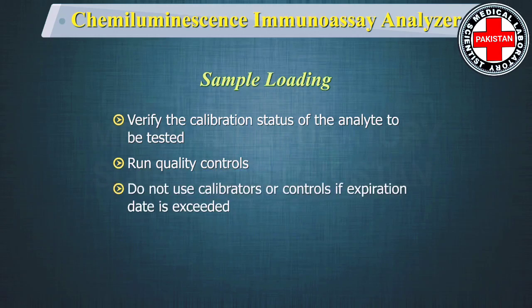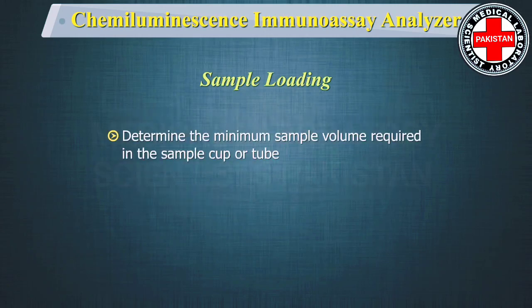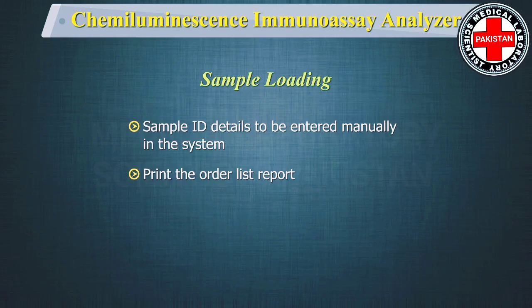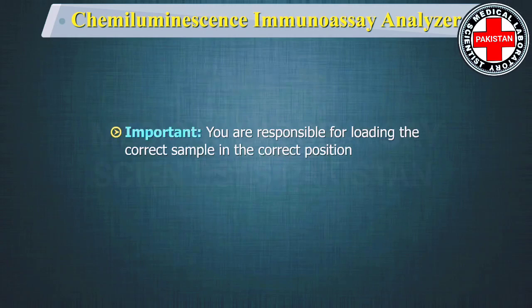Before loading test samples, verify the calibration status of the analyte to be tested. Also run quality controls. Do not use calibrators or controls if the expiration date is exceeded. Determine the minimum sample volume required in the sample cup or tube as described earlier. In a laboratory where the equipment is not connected to the lab information system, sample identification details have to be entered manually. Print the order list report to ensure that you load the samples in the correct carrier position.